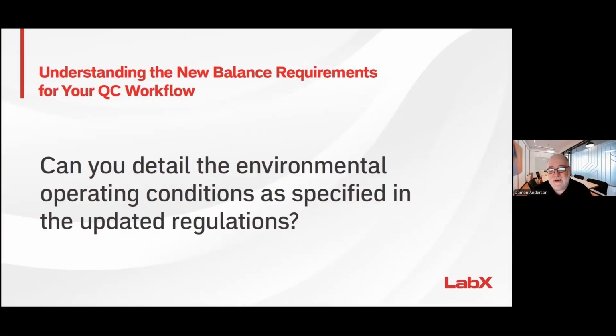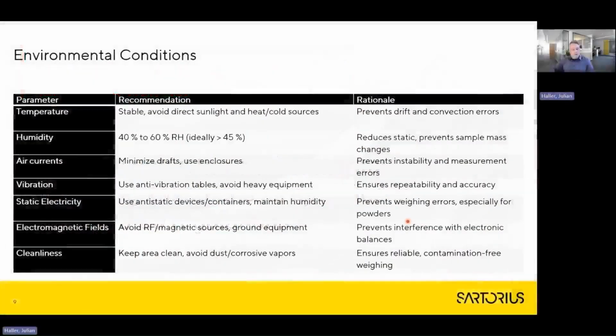Can you detail the environmental operating conditions as specified in these updated regulations? All of the respective chapters give some requirements on environmental conditions. Although the wording and the explicit requirements might vary a little bit, if you follow these requirements, you will be on the safe side. Concerning the temperature, it should be stable, and direct sunlight as well as heat or cold sources should be avoided. Air humidity should be between 40 and 60% relative humidity, and ideally it should be above 45%.